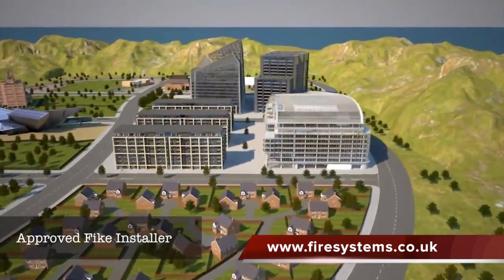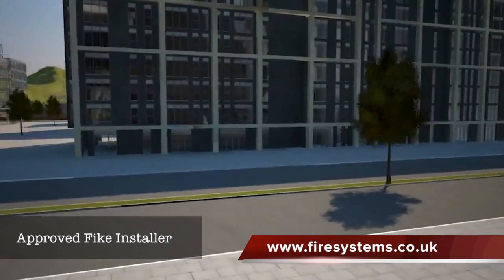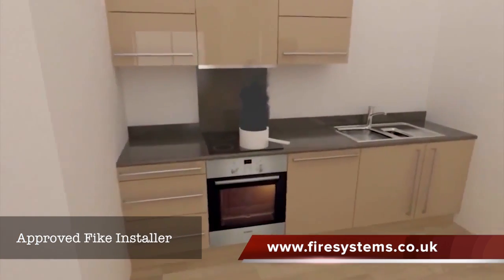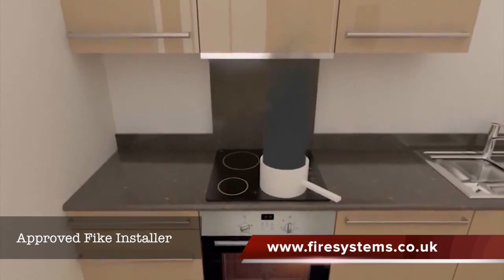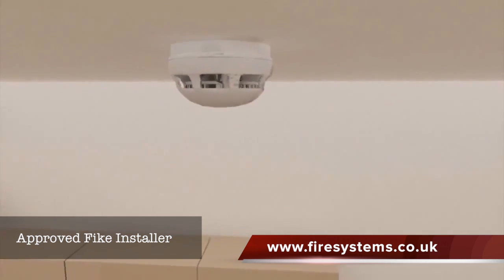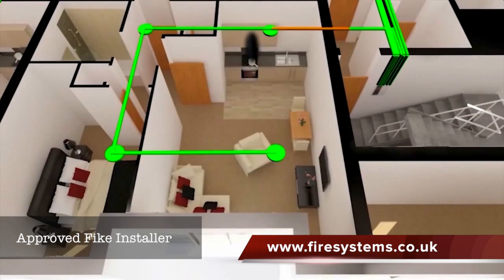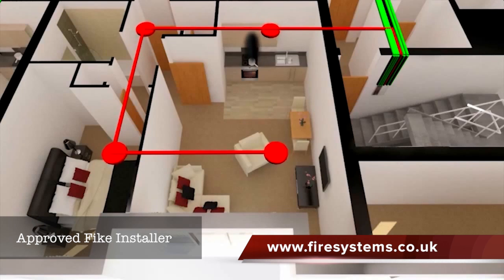Let's see how FIKE's TwinFlex Pro protects you and your residents, both from nuisance alarms and from serious incidents. The resident in apartment 4 has left a pan on the hob, which burns and produces thick smoke. This smoke is detected early by FIKE's multipoint detector with its integral sounder. The detector sends a signal to the TwinFlex Pro panel in the lobby, which instantly activates all four sounders in apartment 4 only, alerting the resident and giving them time to deal with the smoke.